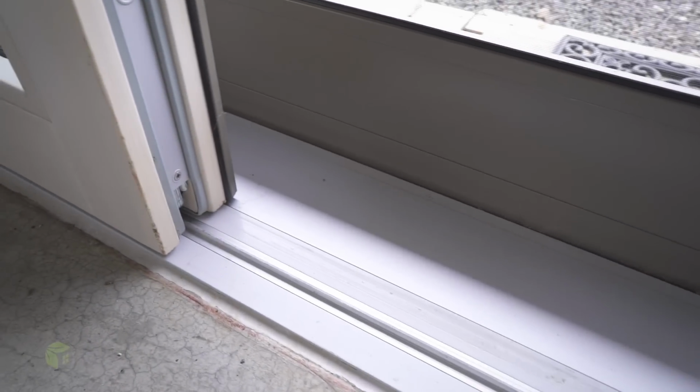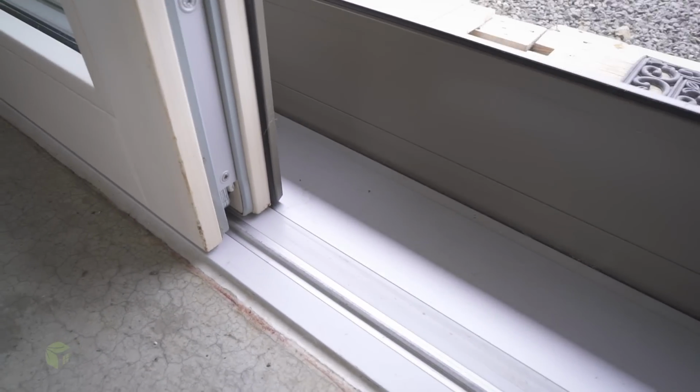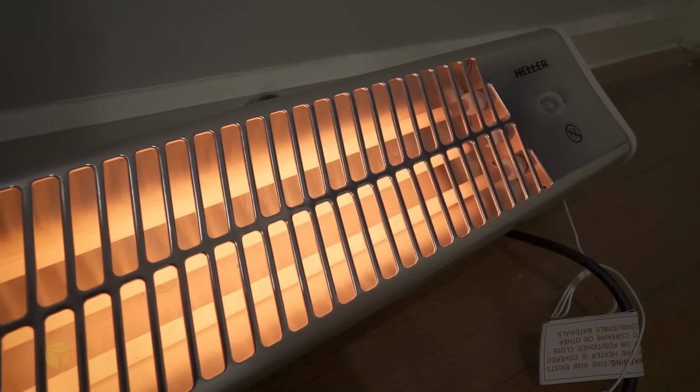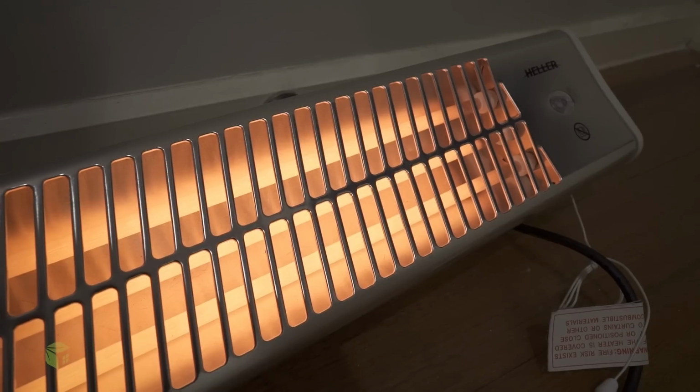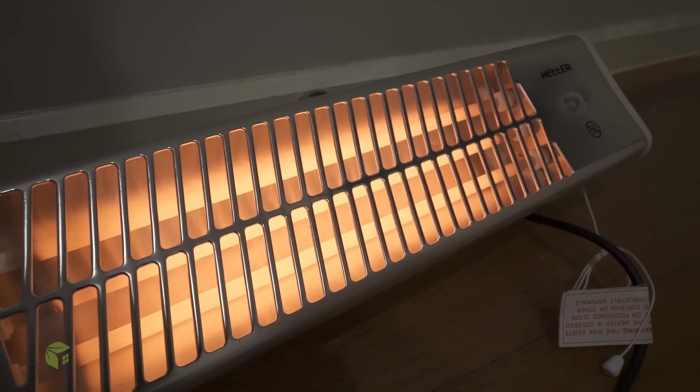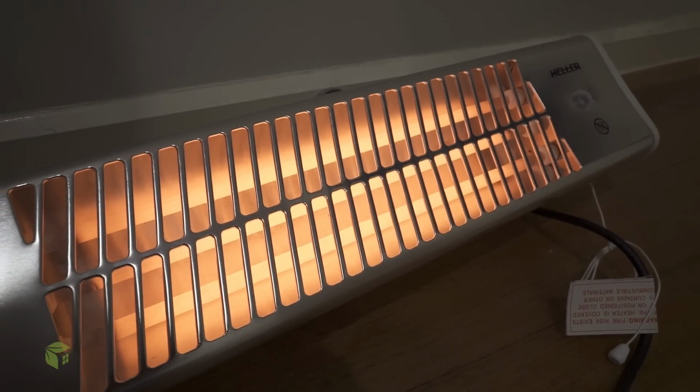So Joseph, if we had a single glazed window here on a 35-degree day, what sort of a heater would we have to introduce to simulate that? Well, it depends on whether you include the direct sun or not. If you include the impact from the direct sun coming through the window, we're talking about a 2 kilowatt heater running in summer when you least wanted heat. So that's what the triple glazed window is doing, benefiting the thermal control of this house.